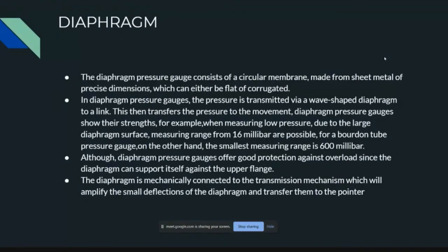Here I am going to explain diaphragm. The diaphragm pressure gauge consists of a circular membrane made from sheet metal of precise dimensions, which can either be flat or corrugated. Corrugated metal diaphragms are ideal for high temperature applications such as mechanical seals, pressure transducers, etc. In diaphragm pressure gauges, the pressure is transmitted via a wave-shaped diaphragm to a link. This then transfers the pressure to the movement.